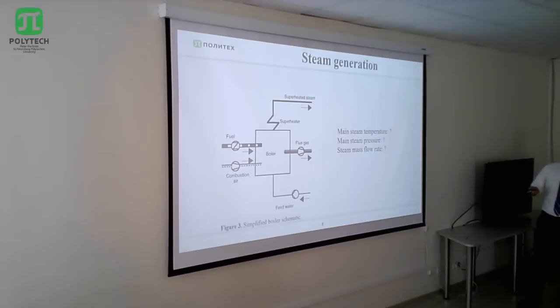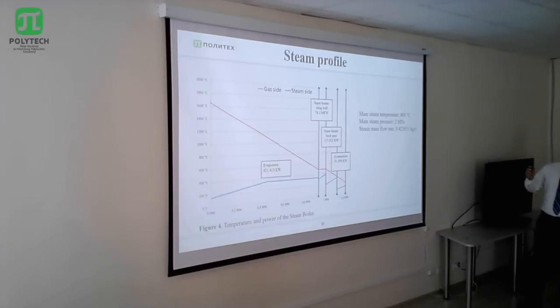Using a simplified schematic for a boiler, I can get, again in an Excel file, the main steam temperature, which will be 400 degrees. Normal big power plants use 500 to 550 degrees, but since this is small scale, this will be the minimum viable temperature for the machinery to work. The main steam pressure will be 2 megapascals, still in the middle range of parameters.